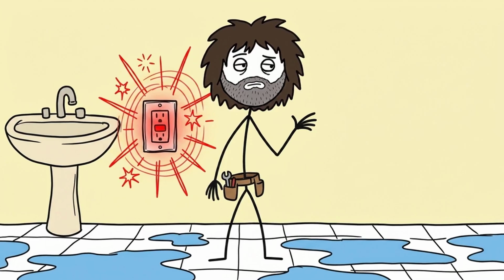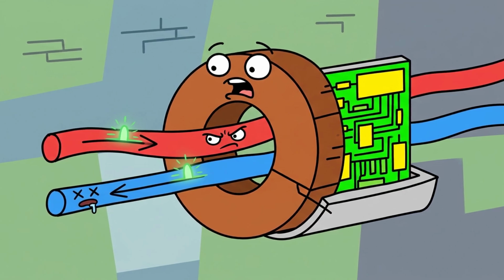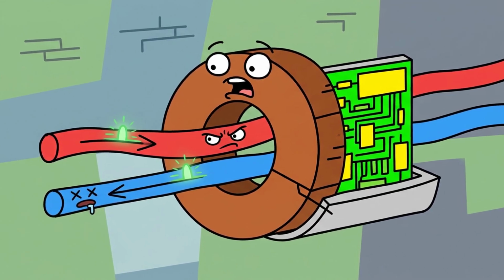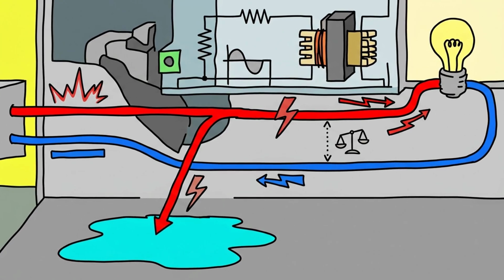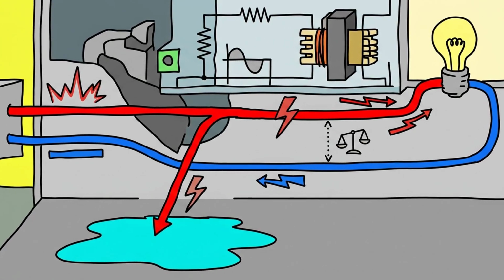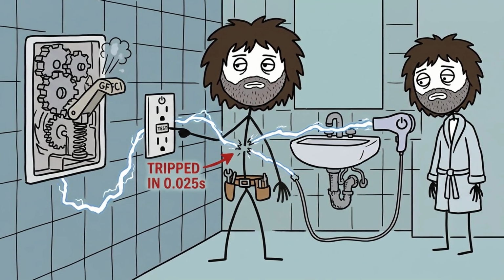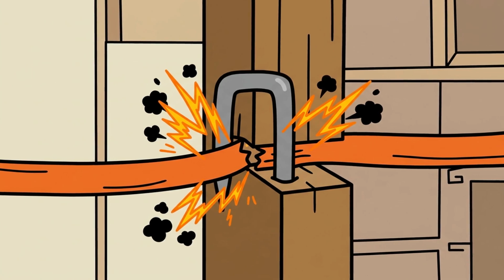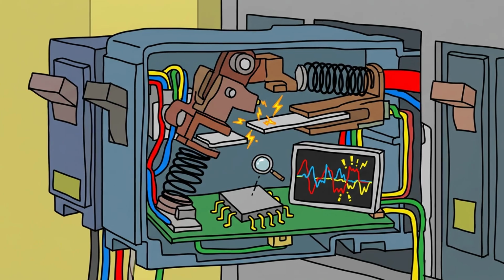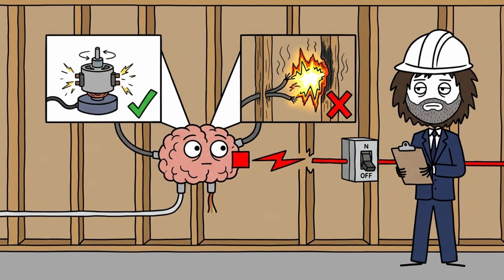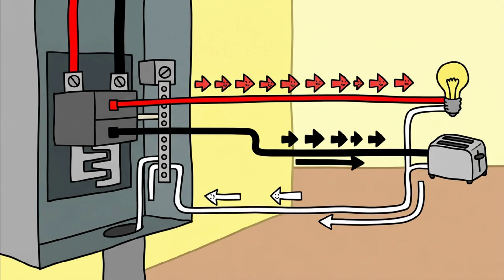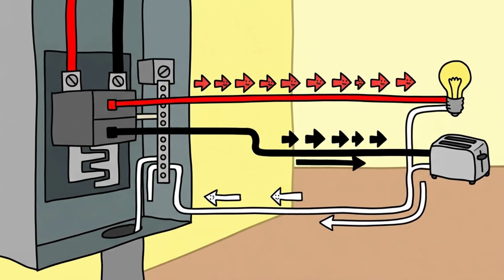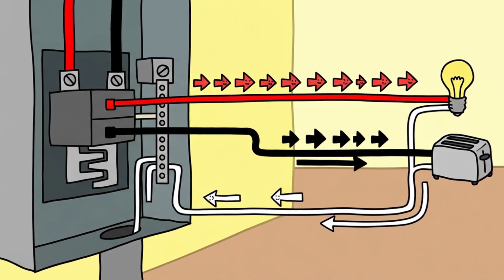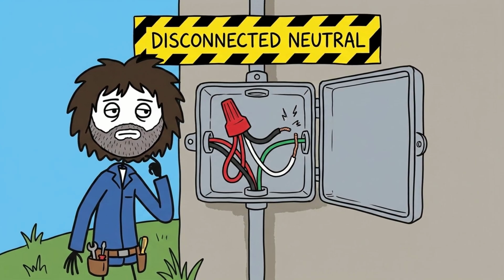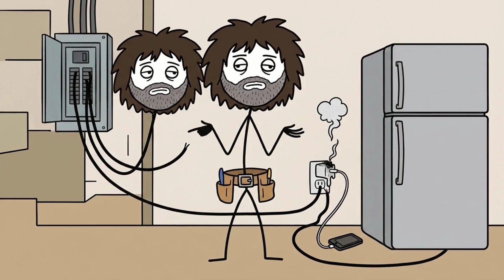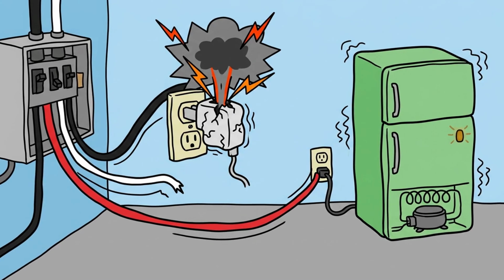To prevent this, national electrical code standards govern exact wire gauge sizes matched to breaker ratings. Standard household lighting and general outlet circuits use 14 AWG copper wire, rated for a maximum of 15 amps. A 15-amp circuit safely handles a continuous load of 12 amps, translating to 1,440 watts. Kitchen appliance circuits, bathroom outlets, and laundry rooms require thicker 12 AWG copper wire paired with a 20-amp breaker. The thicker copper core reduces internal resistance, allowing up to 16 amps of continuous load, or 1,920 watts.